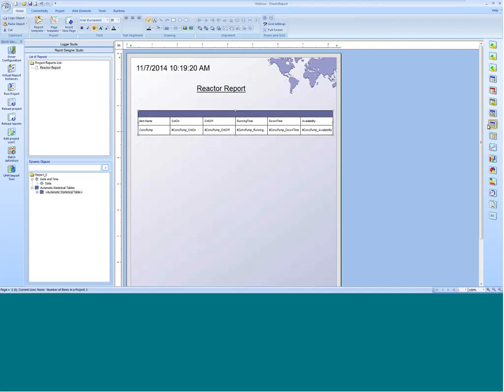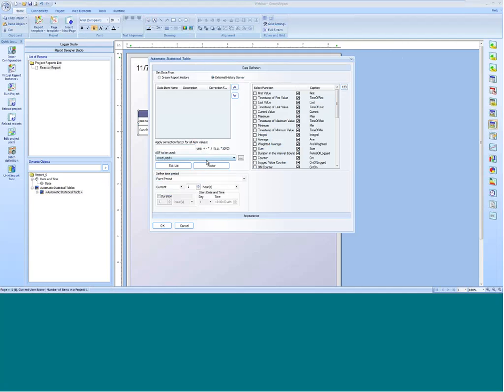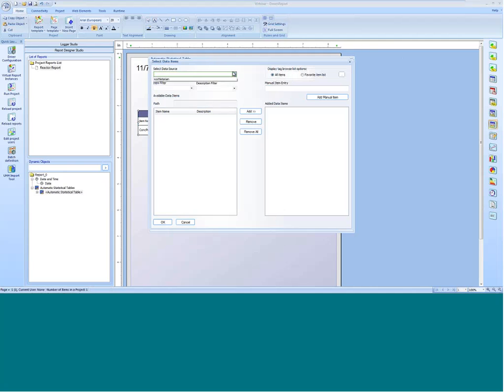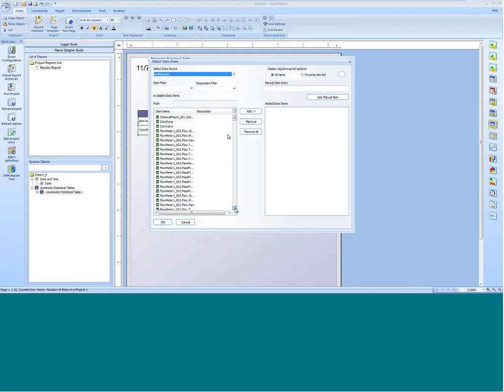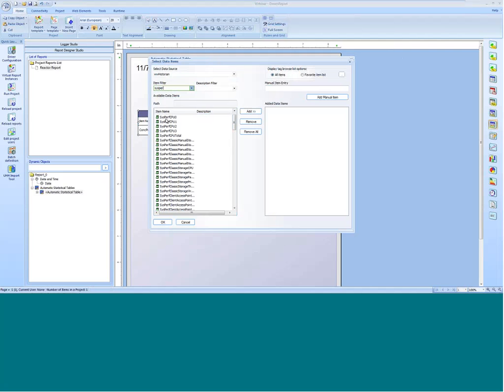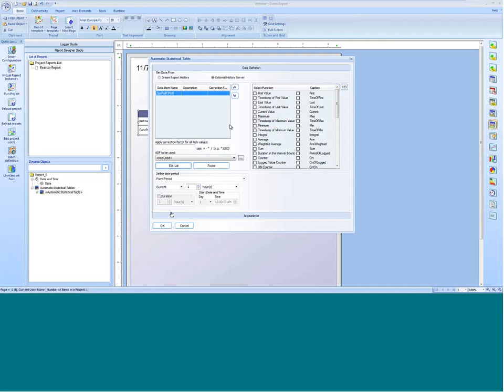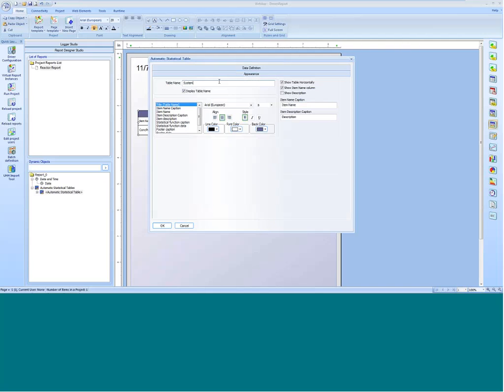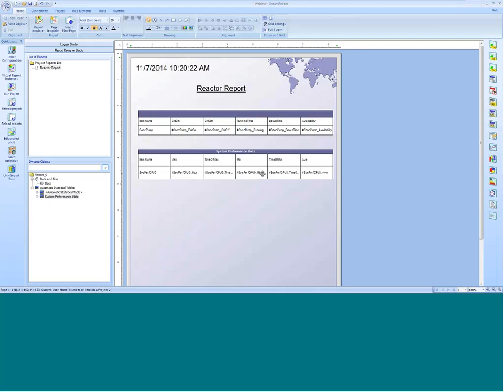I'm going to close this report and continue development. Next, I'll use that same statistical table — instead of an uptime/downtime report, I'll do some statistics on some analog tags. Again I'll choose External History Server, click Edit List, and select the Wonderware Historian. I'm going to use System Performance CPU 0. This time I want the minimum, maximum, the timestamp of the maximum and minimum, and the average. I'll do Fixed Period — 30 minutes this time since I haven't been running for a full hour yet. I'll call the display name System Performance Stats.